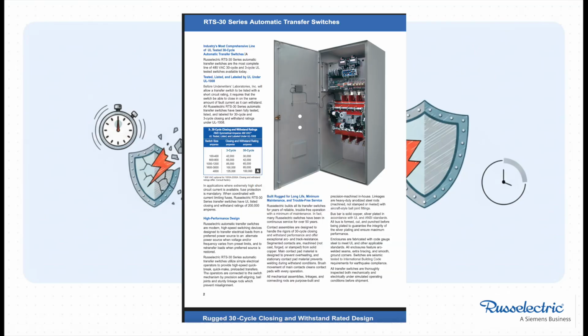The solution is a completely different kind of transfer switch. Instead of only being able to handle a fault for those 3 short cycles, this new type can withstand it for a full 30 cycles. It holds on. It buys the system precious critical time.